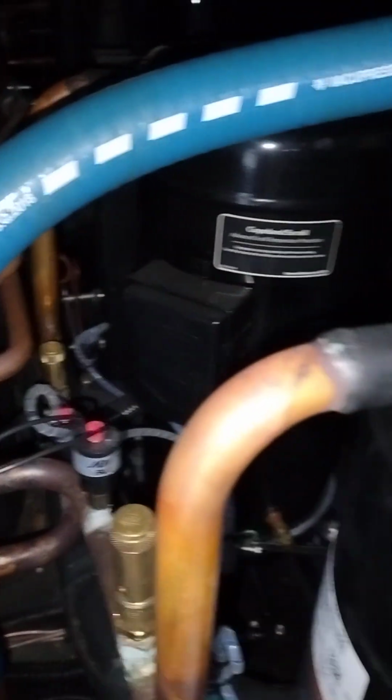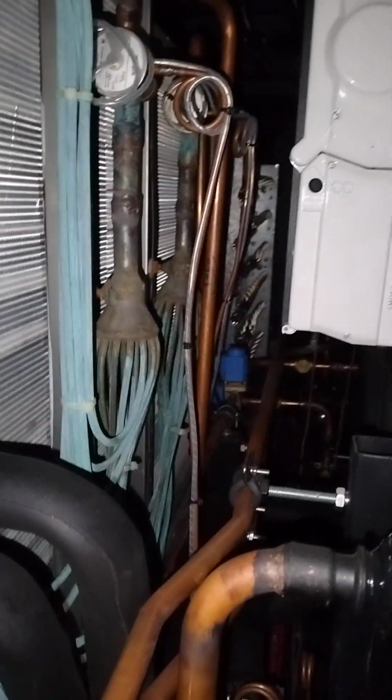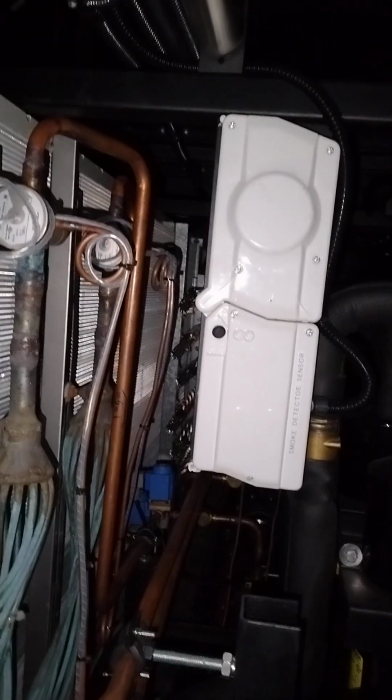This is a unit in which the compressors are actually in the indoor unit, so it's a two-stage compressor system. We have these two stages in there, and we have the evap coil here. You can see the expansion valve and the distributor, some liquid line solenoid valves, and a sight glass. And basically that is the blower, and the smoke detector in there, the white one.